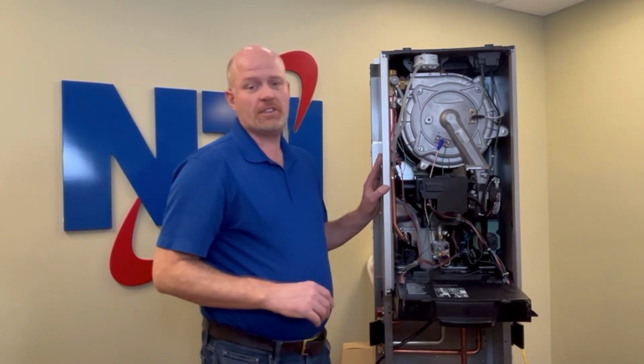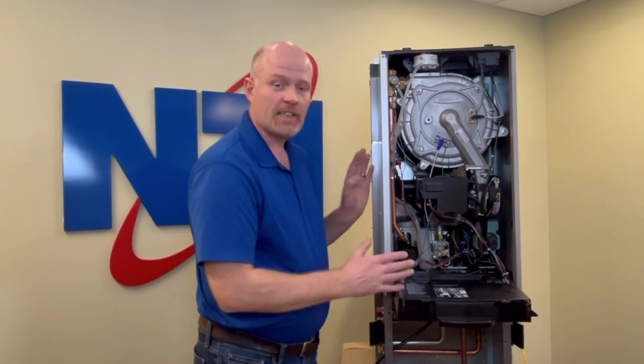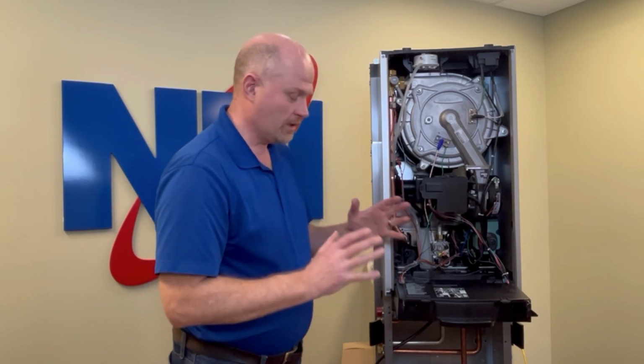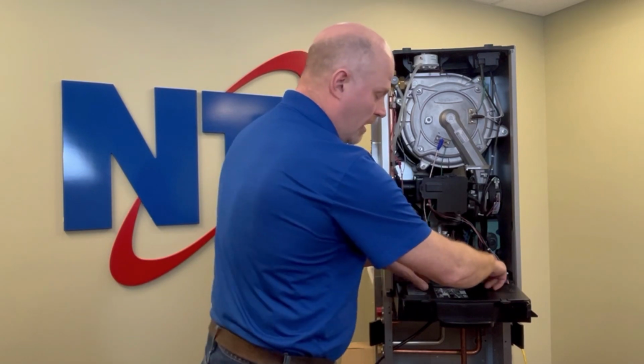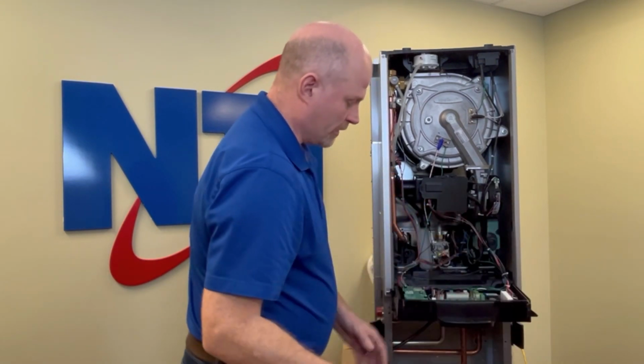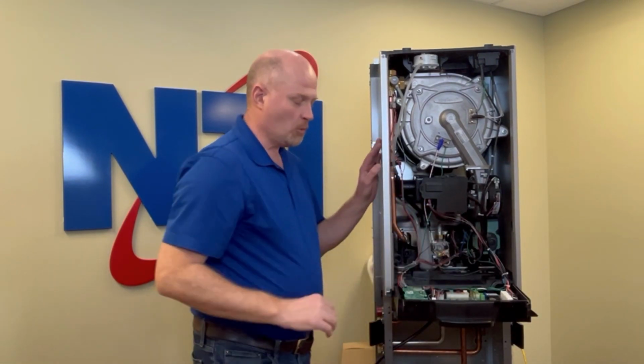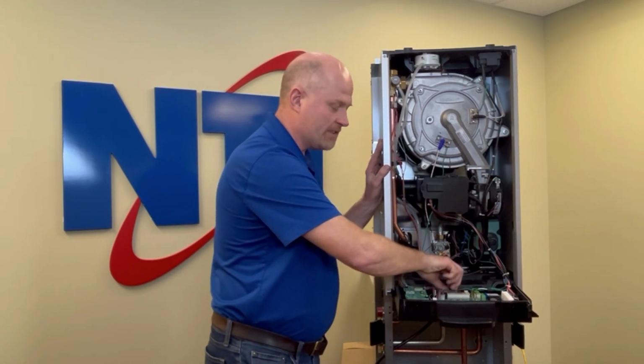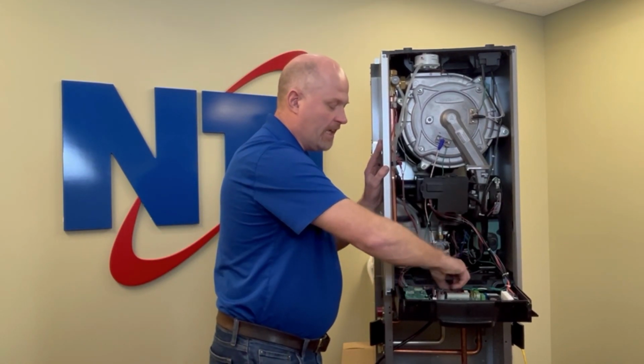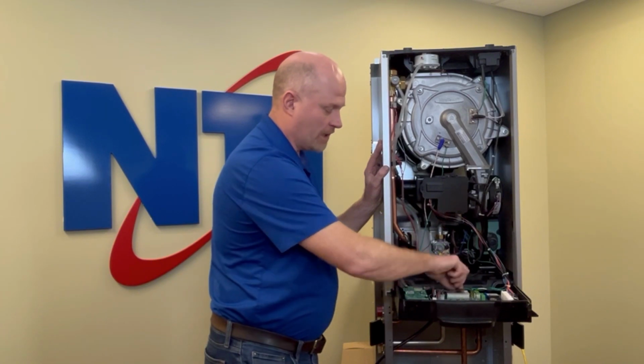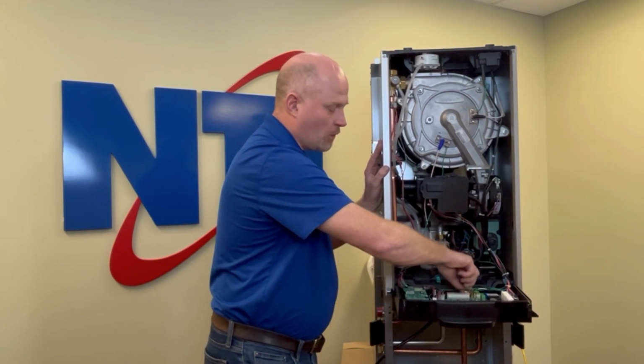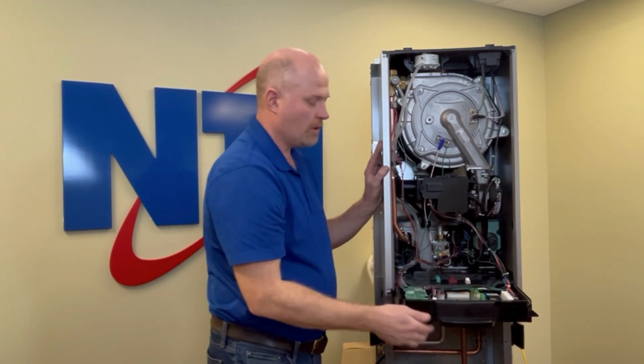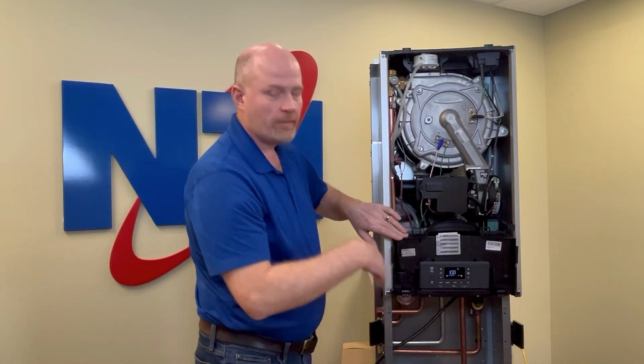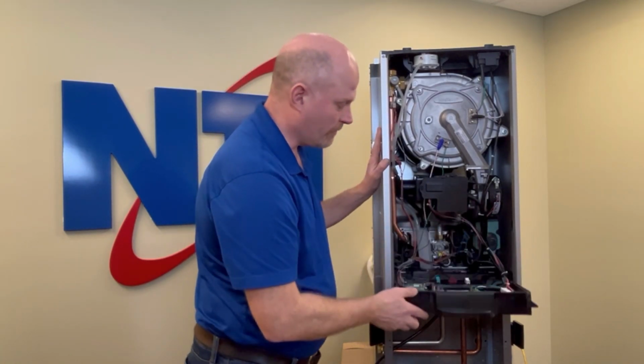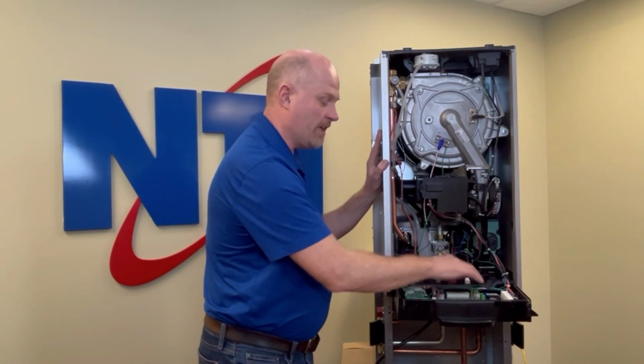The troubleshooting for each of these codes is effectively the same, and that's why I've grouped them all into one video. You want to start by uncovering the low voltage connections on your boiler, and what I recommend is that you disconnect each electrical connector that comes from the outside world, remove those from your circuit board, reset the error code, and see what the boiler does. If your error immediately repeats, the next step will be to check the incoming voltage.